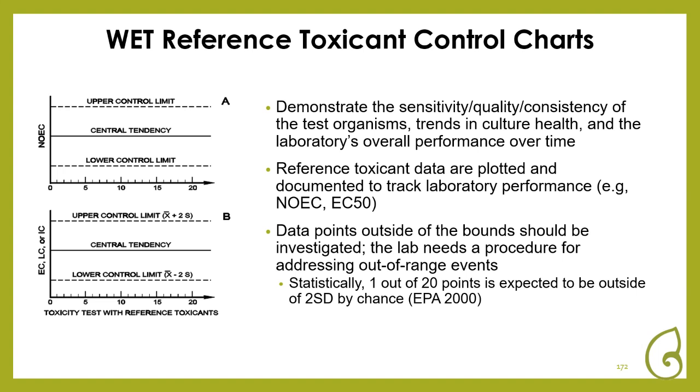Any data points that are outside of the bounds should be investigated, and the lab needs to have a standard procedure for addressing those out of range events. It's also worth noting that statistically, 1 out of every 20 data points is expected to be outside of 2 standard deviations just by chance.